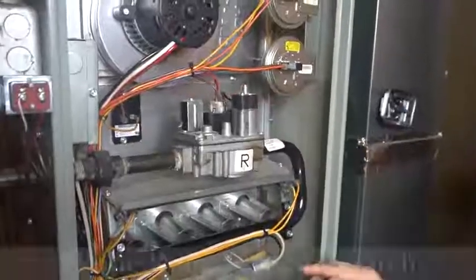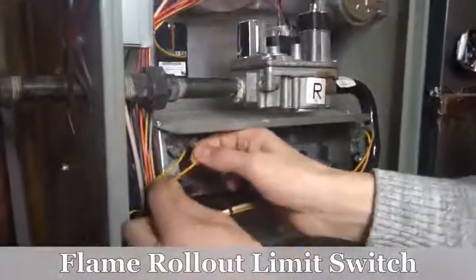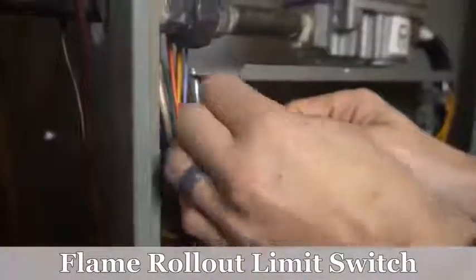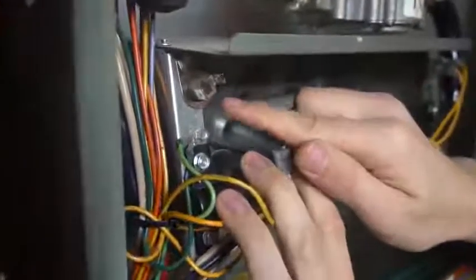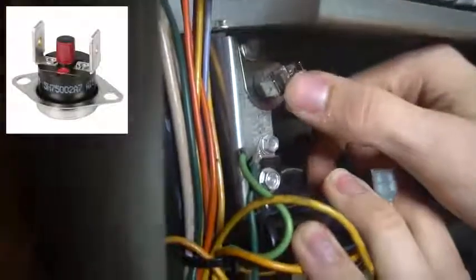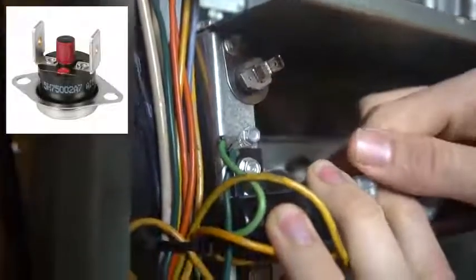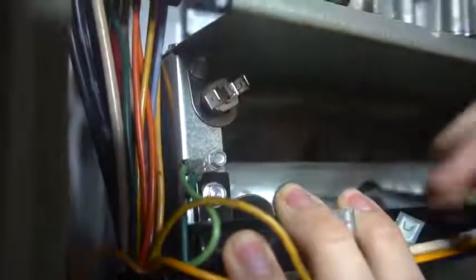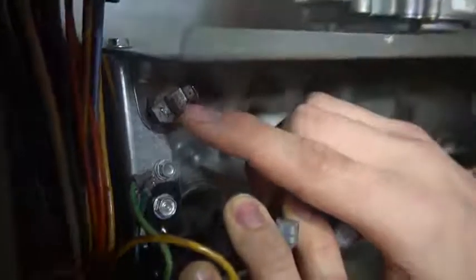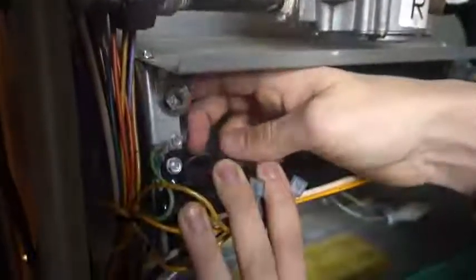And another safety is the flame rollout switch. I have one right here. I can take the wires off so you can see it better. These are usually manual reset switches, because usually if this switch trips, that means something serious is going on and it could be dangerous. The flame rollout switch is also a thermal switch, just like that high limit that we looked at previously. It also gets tripped from heat.